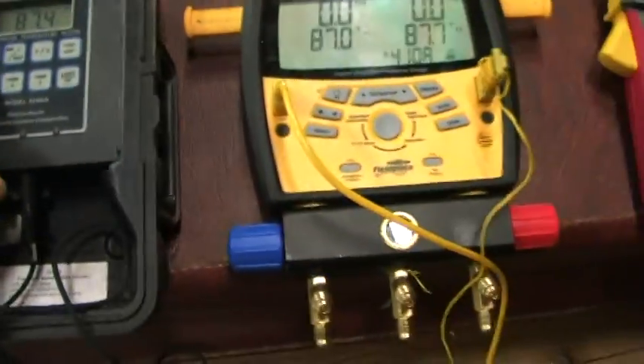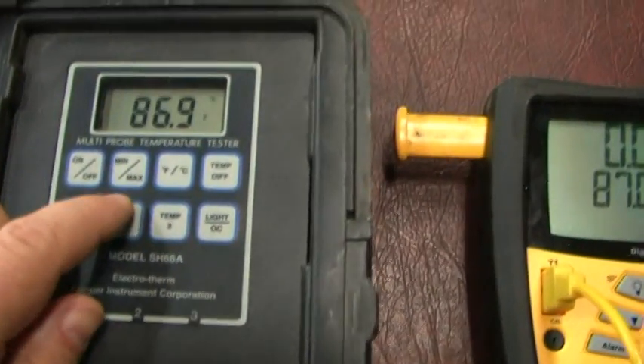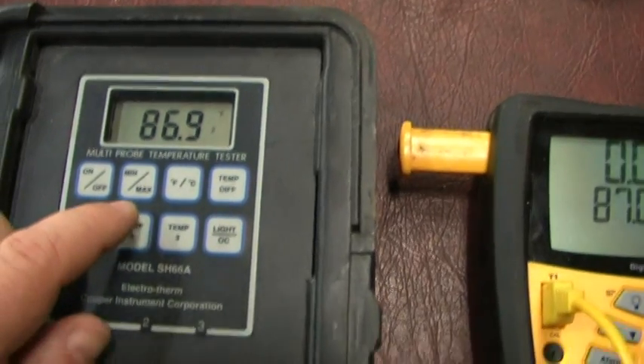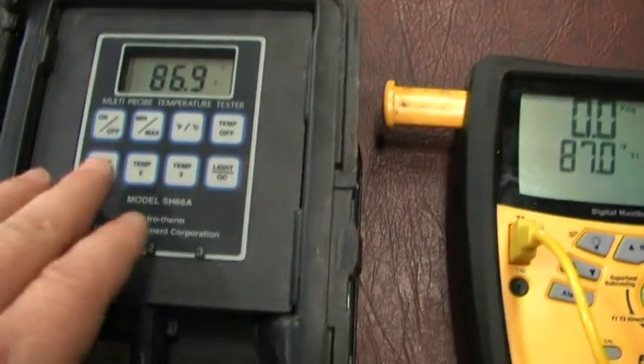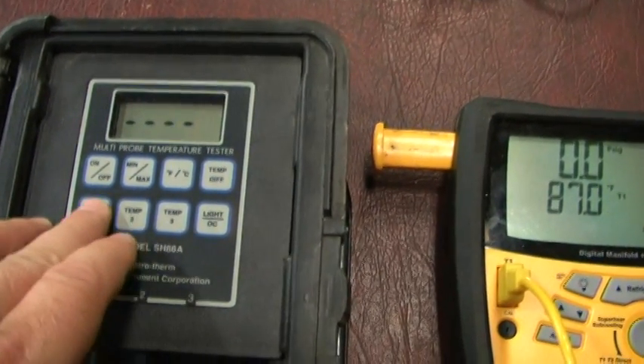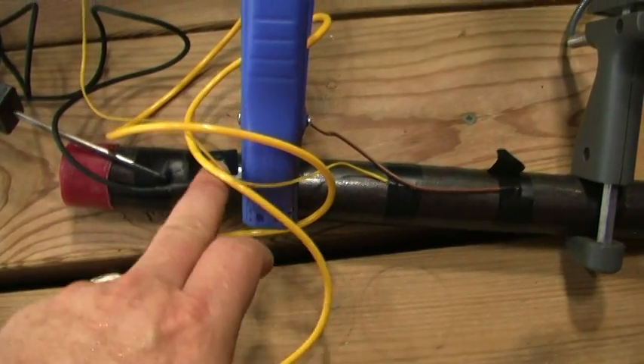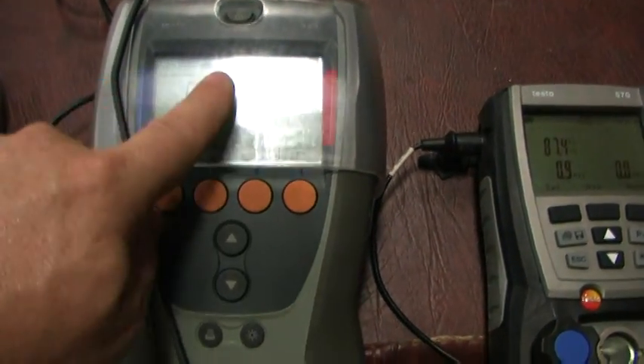Actually here, temp 1 is here, temp 2 - I guess I need to do both of them. 86.9, well shoot, hit the wrong button. 87 for 1, 86.9, so they're within two tenths of a degree. And that's the square tip and just your stick probe. I do want to hook up this other clamp but I have to turn this off, replace the plug and turn it back on, so give me just a minute.